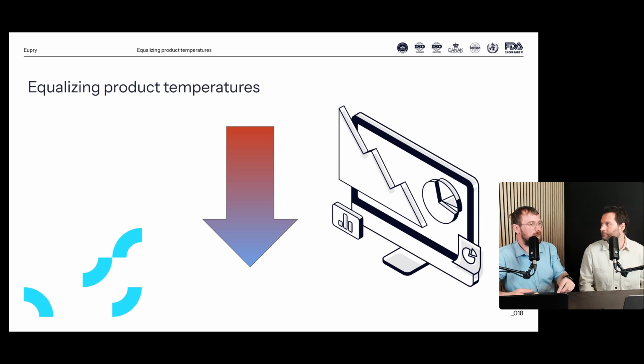That actually meant some of the air that previously moved around due to convection suddenly stopped moving, which caused other issues. Often it's for the better, but we've seen places where it just changes the air distribution inside the facilities. That also means you need to readjust your HVAC system based on those new findings—components you didn't think would impact the control system suddenly do.